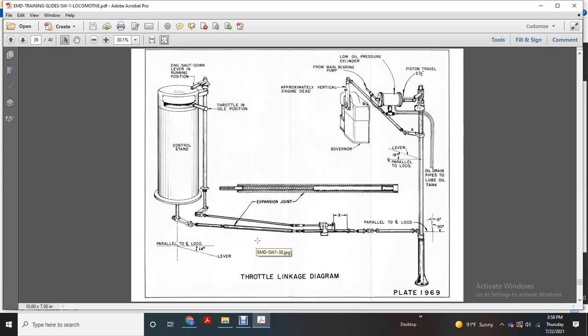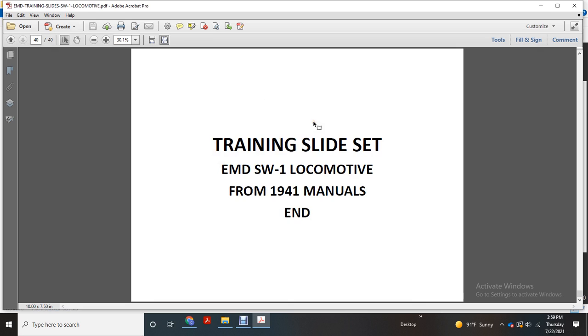Alright, throttle linkage. Show the parallels of the locomotive 14 degrees. You have your control stand, which goes into the engine shutdown lever, running position, throttle position, and then this goes to expansion joints. And then they run parallel to the locomotive at 6 to 90 degrees, and oil drain pipes to the lube oil tank, piston travel, low oil pressure cylinder from main bearing, and approximately vertical engine dead to the governor. And this was train slide set locomotive division SW1 locomotive from 1941 manuals, and that is the end.